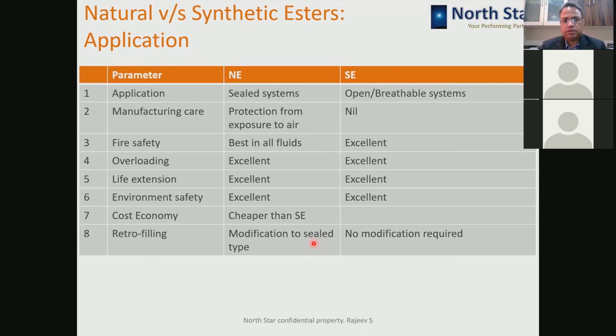However, when a thin film is there, for example on the tap switch or OLTC contact, if the ester is there, then it forms a film which can increase your contact resistance. So care has to be taken that a thin layer of ester is not allowed to dry on live contacts. If you immerse it into the ester volume, then nothing will happen. Okay, so fire safety, as we studied, is best with natural ester, and the second best is synthetic ester. Overloading, life extension, environment safety: both of them are excellent, and they can be used interchangeably for these advantages. Cost economy: synthetic esters are costliest, and natural esters are much cheaper compared to synthetic esters, but costlier than mineral oils. Retrofilling, both the liquids can be used.